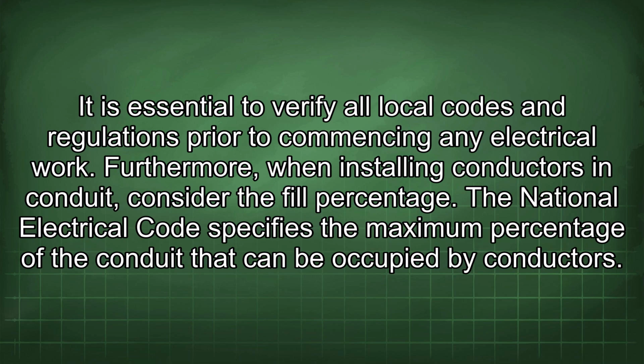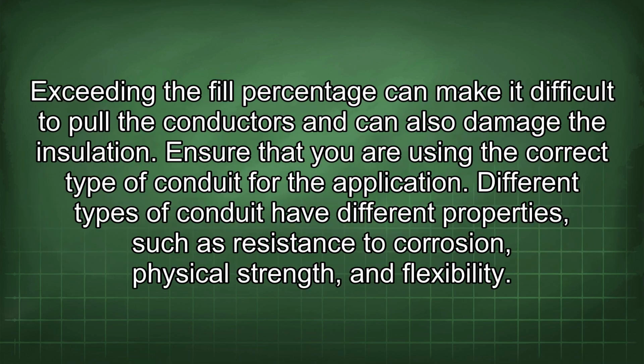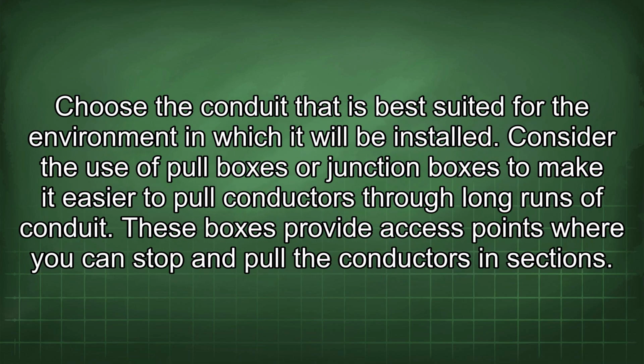Furthermore, when installing conductors in conduit, consider the fill percentage. The National Electrical Code specifies the maximum percentage of the conduit that can be occupied by conductors. Exceeding the fill percentage can make it difficult to pull the conductors and can also damage the insulation. Ensure that you are using the correct type of conduit for the application. Different types of conduit have different properties such as resistance to corrosion, physical strength, and flexibility. Choose the conduit that is best suited for the environment in which it will be installed.